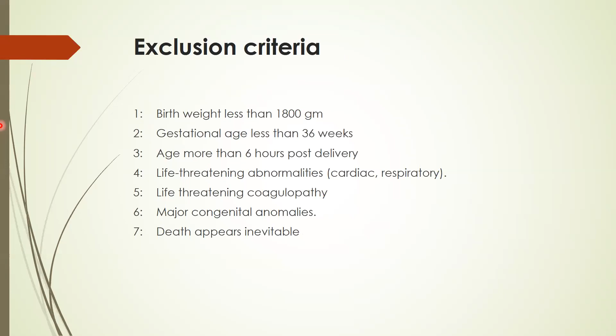So the cooling procedure, I will go quickly. If the baby is eligible for hypothermia, and the baby is still within the first 6 hours, we'll place them in a switched off warmer, and the cooling machine should be prepared, and the baby placed in the cooling device. So in our center, alhamdulillah, we have our total body cooling device. So we'll place the baby. Previously there was selective head cooling, but now most of the centers have total body cooling. The study shows selective head cooling and total body cooling are equivalent. So what is available in your center, you can use.